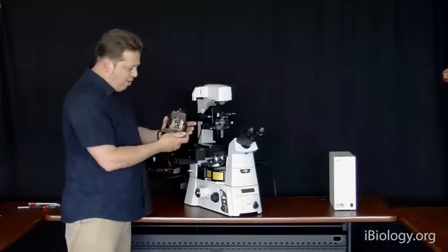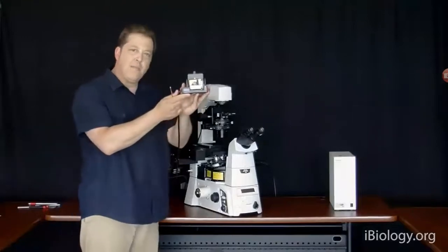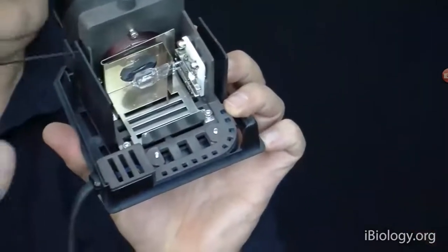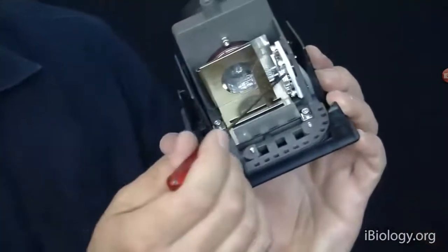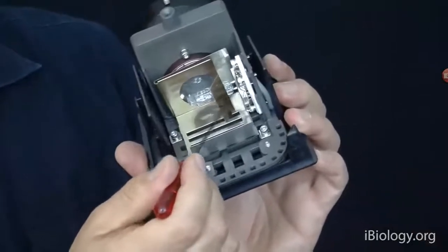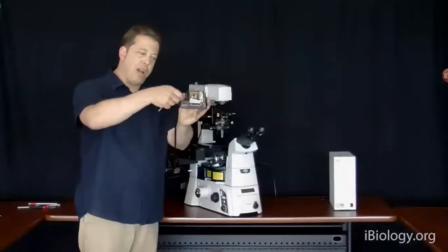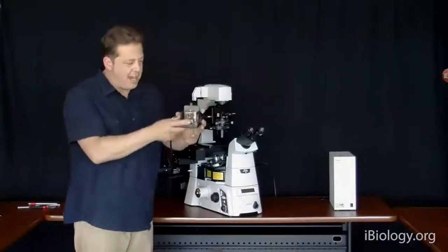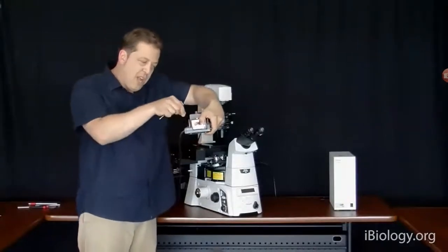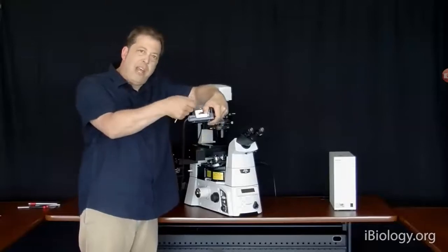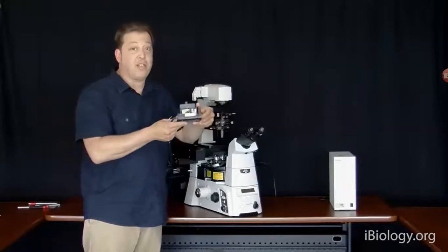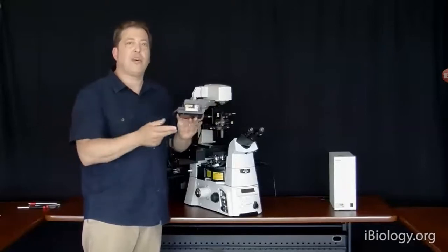And then below that cover, we have this component here. You can see that this component has the halogen bulb held by two metal clips and powered. When you install this bulb in the microscope, you'd want to hold it in the plastic bag it comes in, rip off the bottom of the bag, and then hold down the two clips and put the bulb in and then pull the bag off. You'll never want to get the oil on your fingers on that bulb. That could cause the bulb to fail.